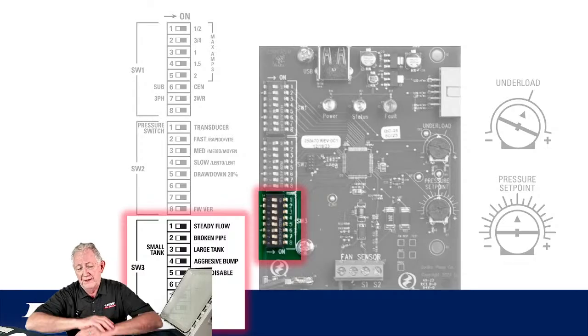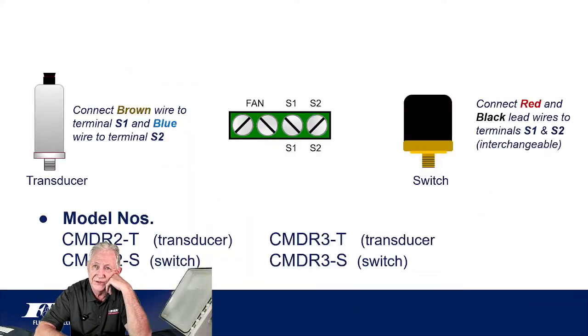I'm just sharing some opinions I've heard over the years from contractors as it pertains to transducers and switches. A lot of them tend to prefer a transducer, and one of the reasons is it's easier to set that pressure set point. I'm going to back up to the slide I think I had, Renee, where I showed the pressure switch on the right-hand side.